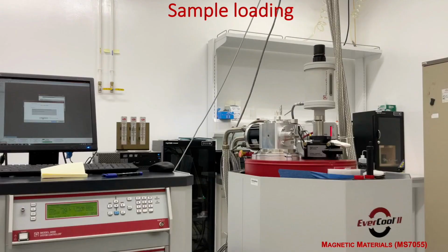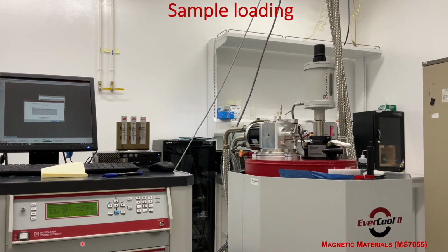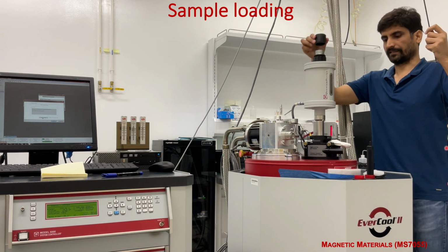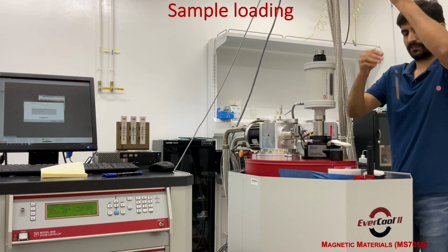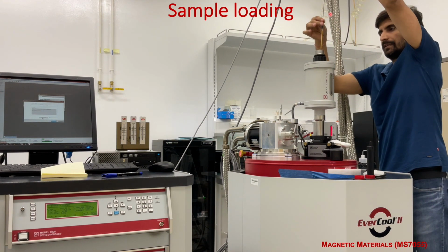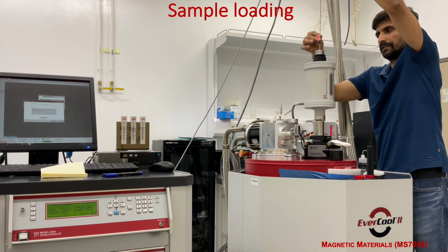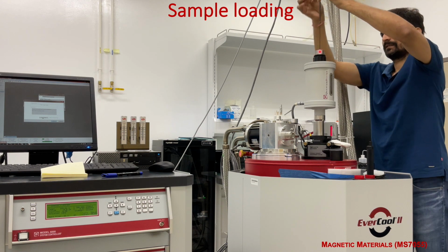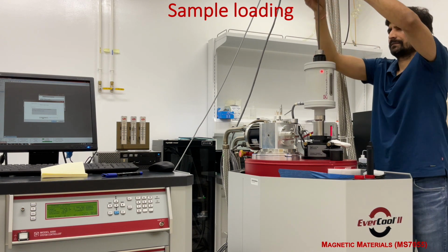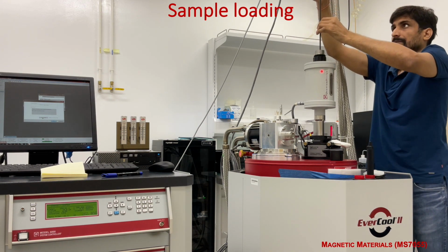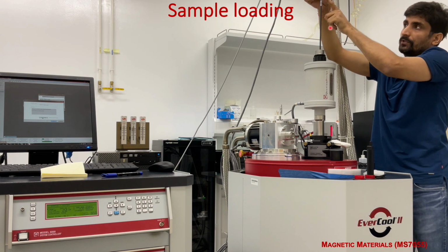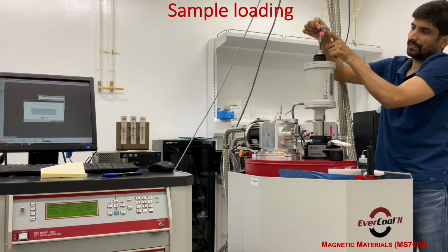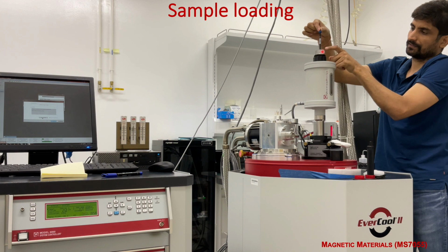Next is loading the sample. To load the sample, what we do is, you see here that we have a long sample tail, and this is the sample here. It's going inside slowly, and at the top we have a magnet in this portion, and here also a magnet.